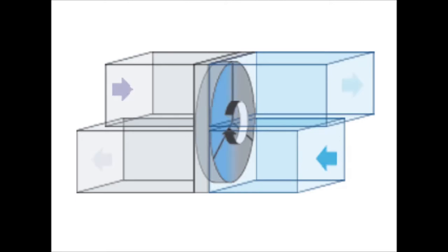The air going into the room is then already filtered. And there's air coming back from the room and leaving the air handler with the help of a fan, which may have a filter, and that's often not as robust a filter as the one installed for the fresh air. Sometimes you'll have a third bank of filters, after the air coming back from the room and the air coming from the outside are mixed together, and then it goes through another bank of filters. That also happens sometimes.